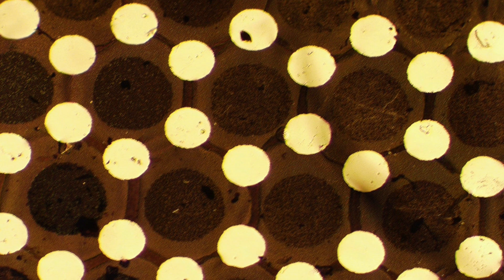How do you fabricate your implant? The implants are fabricated just as the most advanced microchips that you would find in your computer. They are formed by stacking atomic layers one upon the other. The implant is a small rectangle of a ceramic oxide which is 1.6 millimeters by 3 millimeters with a thickness of approximately 1 micron. It may contain up to 10,000 stimulating areas.